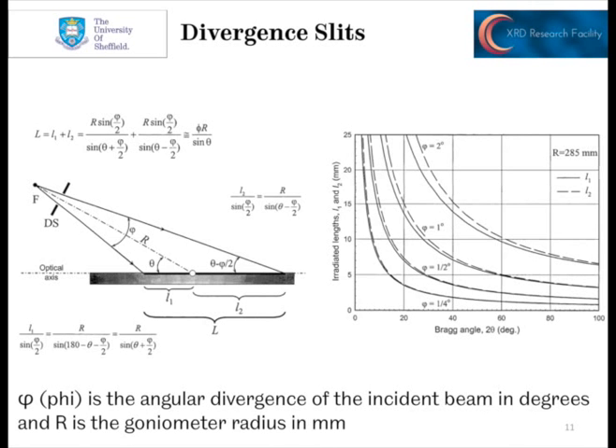The take-home message is that if you have a peak at 20 degrees 2-theta, most machines have a 1-degree divergence slit. At 20 degrees, L2 would be about 15 millimetres and L1 about 13 millimetres, so the total X-ray footprint from left to right across the machine would be around 28 millimetres. That explains why we need such big samples for X-ray diffraction. If you have a very small sample, you could decrease the slit size — moving to half a degree slits, the total illuminated area drops to around 14–15 millimetres at 20 degrees 2-theta. But for Bragg-Brentano geometry, bigger is always better in terms of samples.